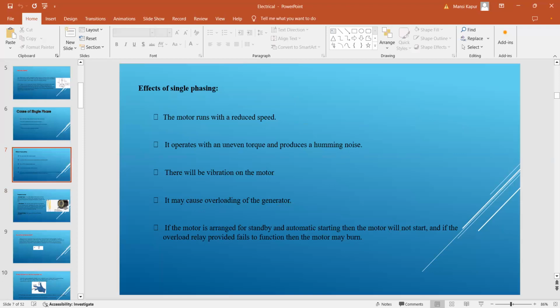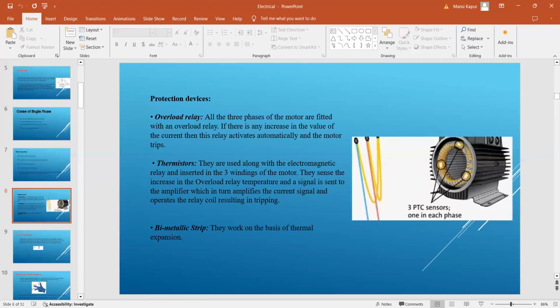So now tell me, what all protections are provided on a motor? What all protective devices are provided on the motor? So these are the protections provided on the motor. First one is the overload relay. All three phases of the motor are fitted with an overload relay. They measure the value of the current. If the current value is increasing, then this relay activates and automatically the motor trips.